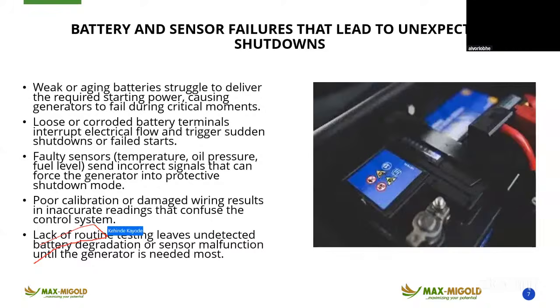Loose or corroded battery terminals interrupt electrical flow and trigger sudden shutdown or failed start. So when your batteries are loose, when they are not properly firm, and you want to start your generator, you will assume that everything is fine, but they may fail you. So ensure the needed maintenance is carried out on a regular basis. Either daily, you check the battery terminals, check their firmness to the battery head, and all that will keep your battery running.